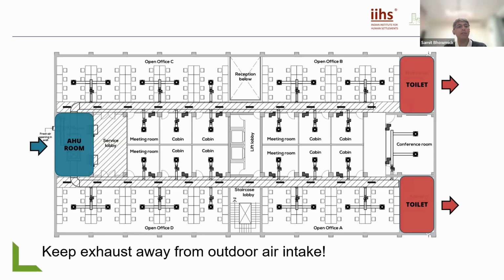Having said that, nothing is impossible. You can look at how to integrate a new chill water system, how to bring that chill water, which is a different temperature loop, into the space. If an existing building doesn't have sufficient shafts, these are all going to be issues. And of course, in the end, your costs are going to be high, so you'll have to evaluate that before you propose this to a client, or consider it within your own project.